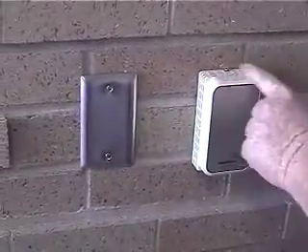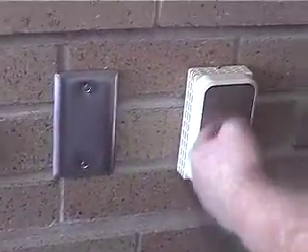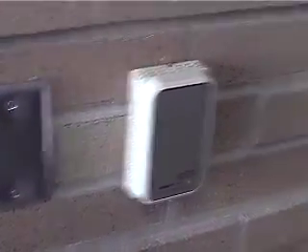Real quickly, while we're on the stairwells, I just want to go over some of the fan coils in here. This is the controller for the fan coil, and you notice that it does not have an adjustability knob. We've set all of these right around 72 to 75 degrees, so that's where they're currently set. If you need to adjust it, you can take that cover off, unscrew it with an Allen key, and it is adjustable. It's just not designed for the students to tamper with.